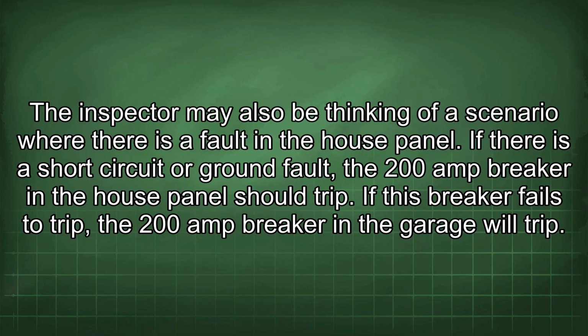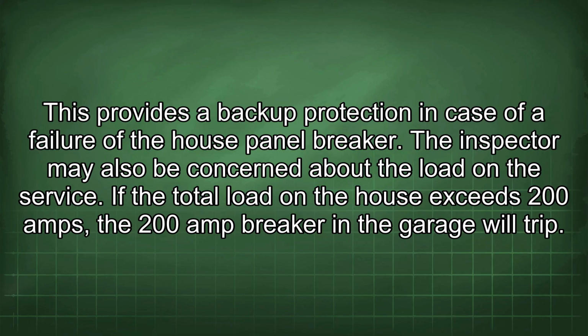The inspector may also be thinking of a scenario where there is a fault in the house panel. If there is a short circuit or ground fault, the 200-amp breaker in the house panel should trip. If this breaker fails to trip, the 200-amp breaker in the garage will trip. This provides a backup protection in case of a failure of the house panel breaker.